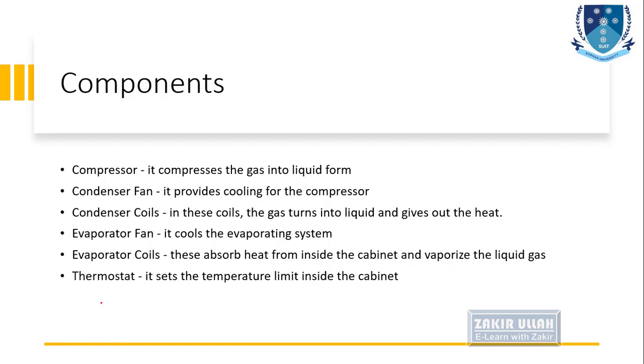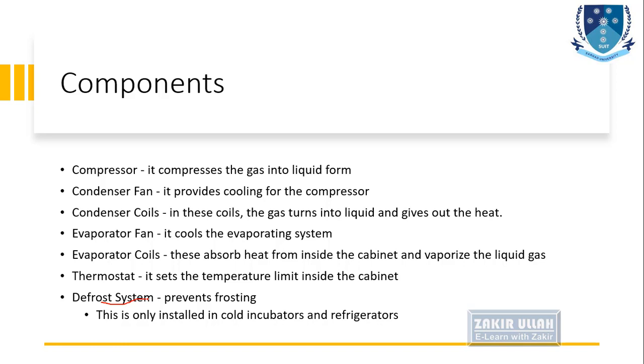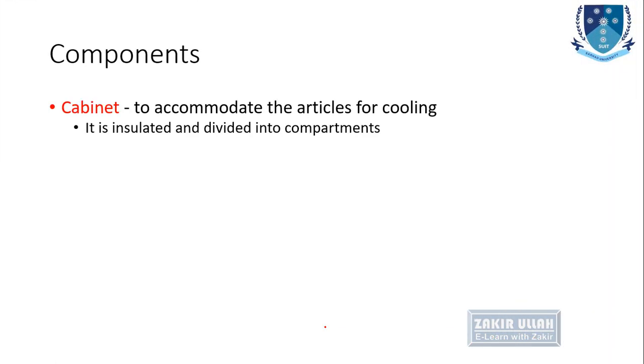Thermostat is the part which sets the temperature limit inside the cabinet or inside the incubation chamber. Defrost system is a system which prevents frosting or freezing. This is only installed in cold incubators and refrigerators. The cabinet is the area in which articles are placed for cooling, and it is insulated and divided into different compartments.